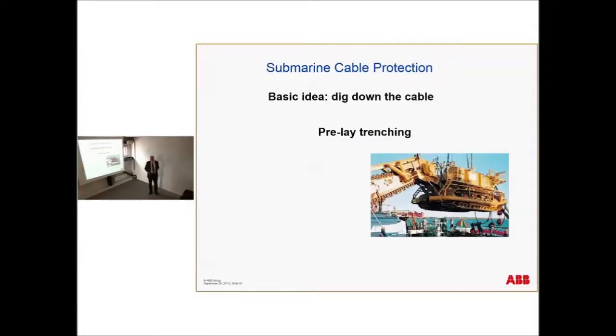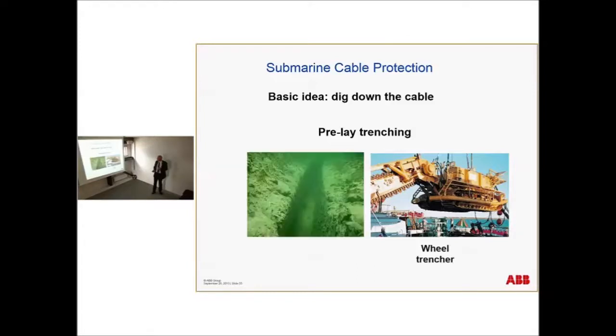When it comes to protection, the basic idea is to dig down the cable so it can't be exposed to mechanical damage. You can have a trencher. You can see here, this is for trenching also through soft rocks. It's like a big motor saw that can trench also through sandstone, etc. Normally you want to have the cable buried at least 1 meter below the seafloor.